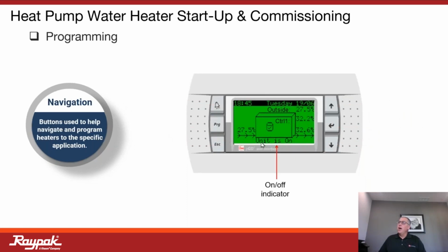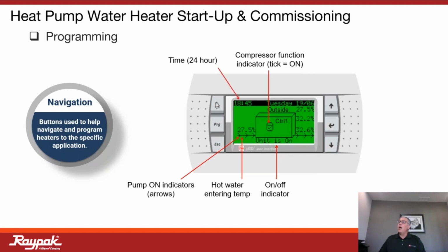On the display itself, there's a lot of usable information. You'll note that right here, as we get this unit, sometimes they come to us where they are defaulted in Celsius, and we'll talk about programming, how to get it to change it back to Fahrenheit. It'll also give you pressure readings in kilopascals, and we can get that back to PSI, and we'll talk about changing those units of measure. But there is a visual indicator that the unit is on. You'll see the entering water temperature, you'll see the exiting water temperatures, and a 24-hour time clock if you've taken the time to set that up in the display.